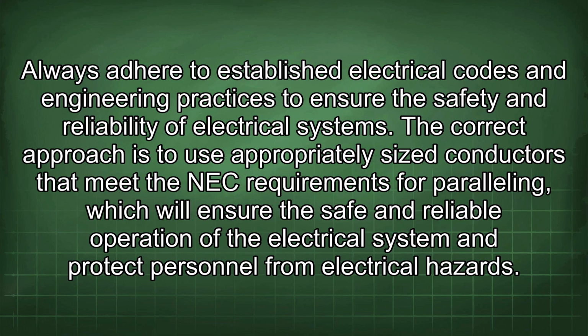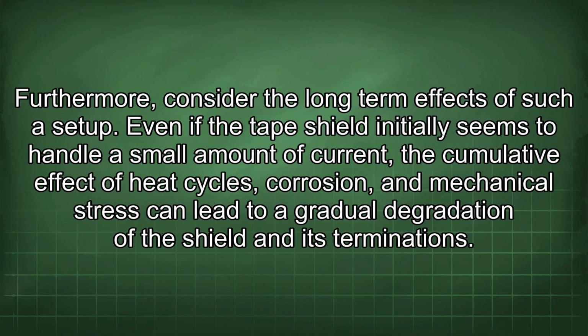The correct approach is to use appropriately sized conductors that meet the NEC requirements for paralleling, which will ensure the safe and reliable operation of the electrical system and protect personnel from electrical hazards. Furthermore, consider the long-term effects of such a setup. Even if the tape shield initially seems to handle a small amount of current, the cumulative effect of heat cycles, corrosion, and mechanical stress can lead to a gradual degradation of the shield and its terminations.